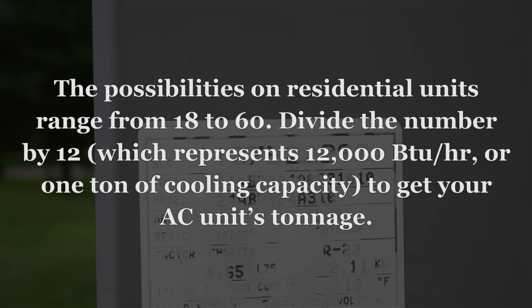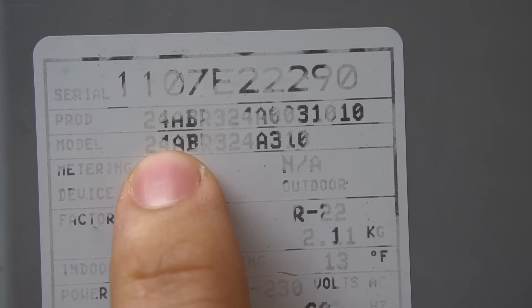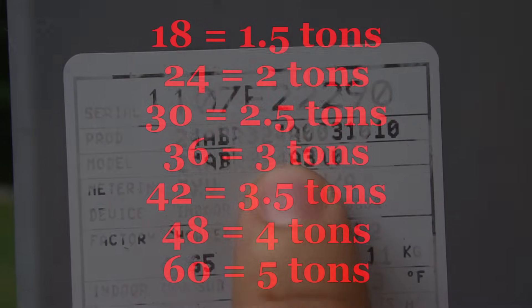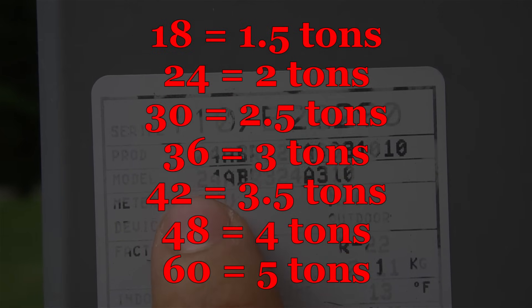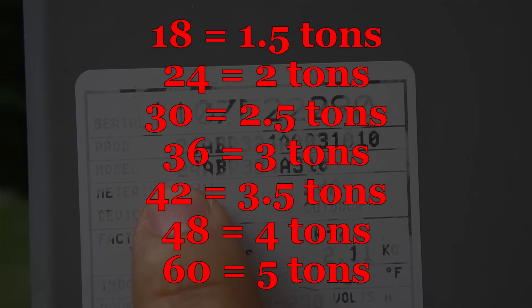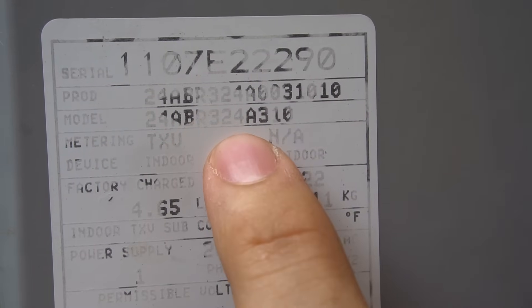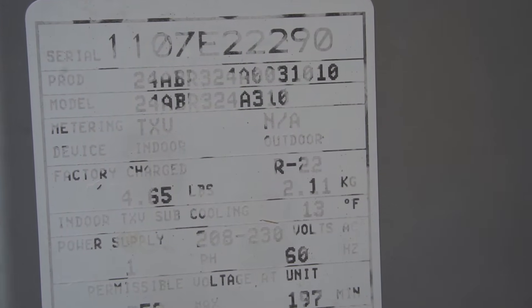And there's also halves. So there's 1.5 ton, 2.5 tons. For example, if it was an 18 right here or in the middle, that would be a 1.5 ton unit. Or in my case, it's a 24. That means it's a two ton unit. So there you have it. That is how you read the tonnage of your air conditioner outside.